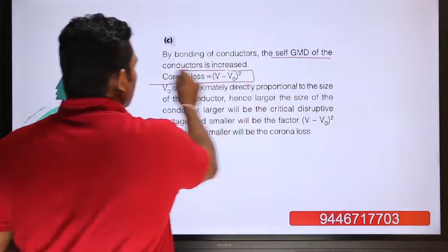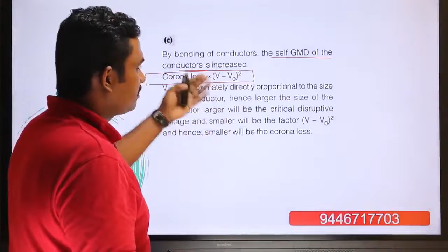Corona loss is proportional to (V - V0) squared. V0 is approximately directly proportional to the size of the conductor, so the larger the conductor size, the larger the critical disruptive voltage, and the smaller the factor (V - V0) squared becomes, resulting in smaller corona loss. So we need a larger net size of the conductor, which can be realized by using bundle conductors.